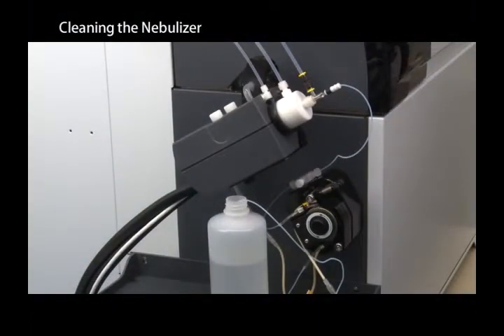For normal cleaning, place your nebulizer in a 5% nitric acid solution. Leave micro-mist nebulizers for about 10 minutes and PFA nebulizers for a few hours, or until the monitored signal drops to the required level.